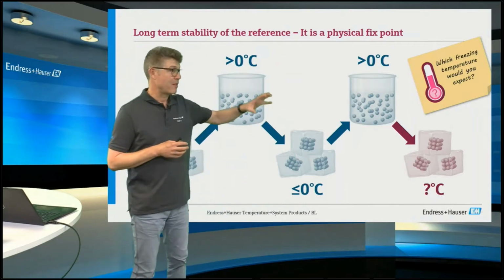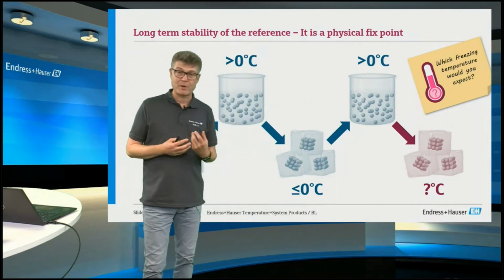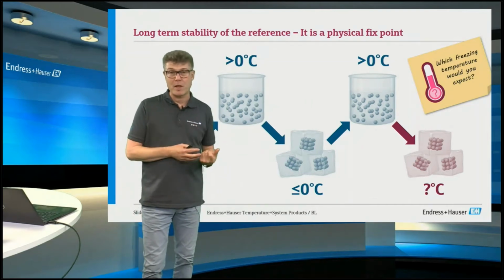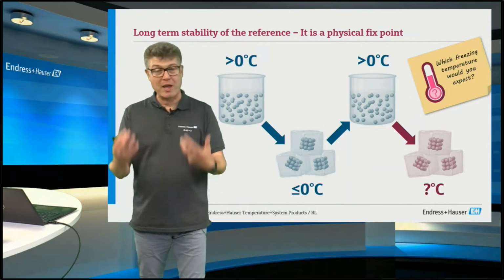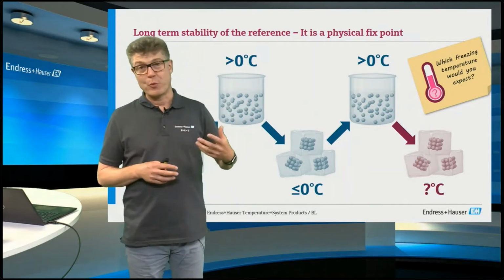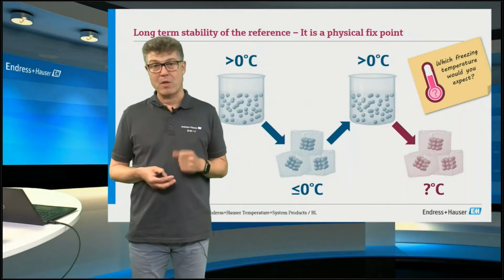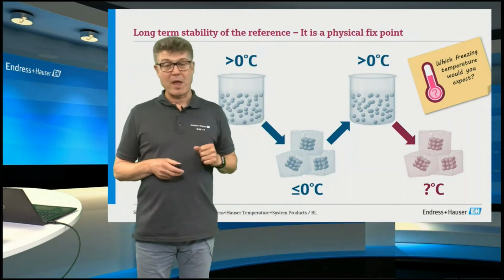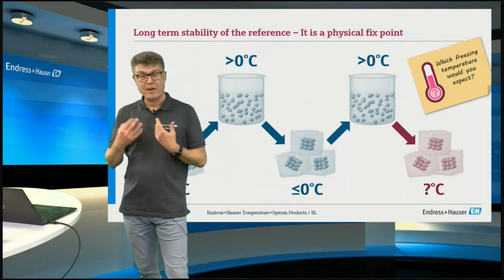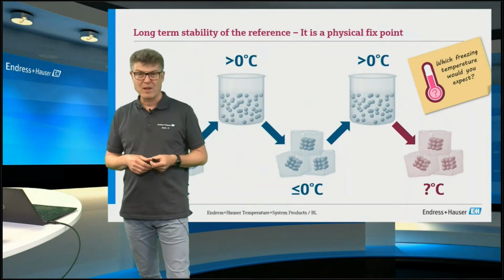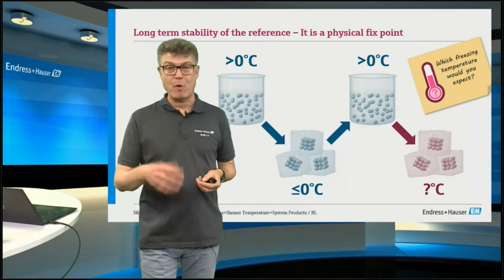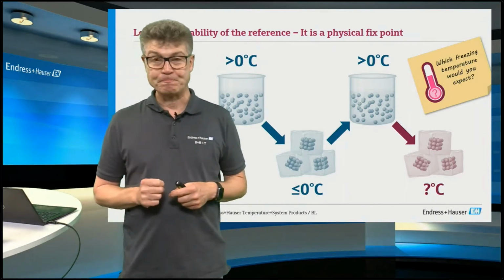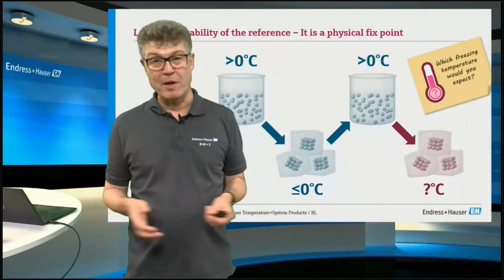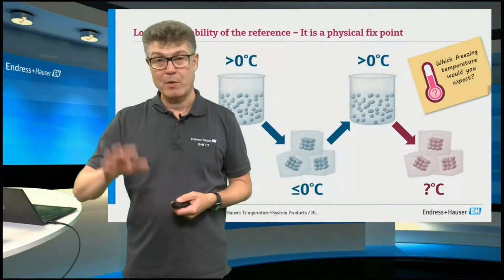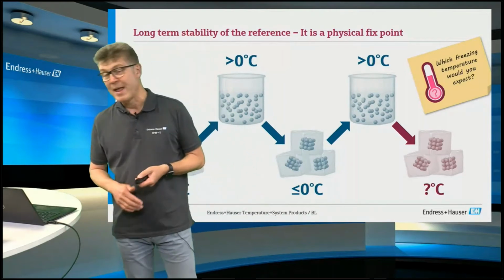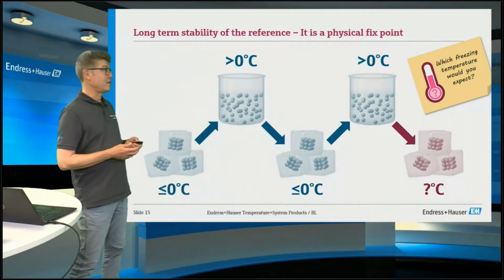And the job of the Curie crystal is to do the calibration of the PT100. And the PT100 can change, it can drift. We come to this later. And that is the reason that you need to do a calibration of the thermometer. So, we have tested it, not ourselves. We've given it to an institute. And as far as I remember, they have performed 40,000 calibrations. And as a result, we have a certificate about the long-time stability, which you can show to your auditor if you're using this instrument. That is the idea behind it.